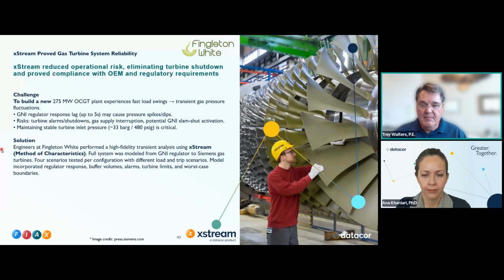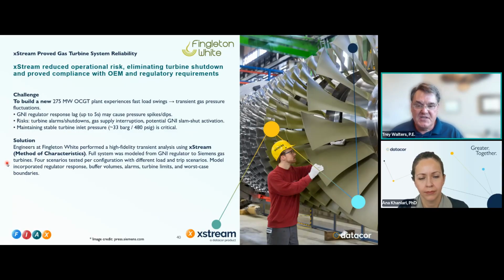Again, they used xStream, high fidelity transient analysis, full system. xStream uses the method of characteristics, for those of you who are into geeky computational things like me. The full system was modeled from the GNI regulator to the Siemens gas turbines, with 4 scenarios tested per configuration with different load and trip scenarios. The model incorporated regulator response, buffer volumes, alarms, turbine limits, and worst case boundaries. Okay.